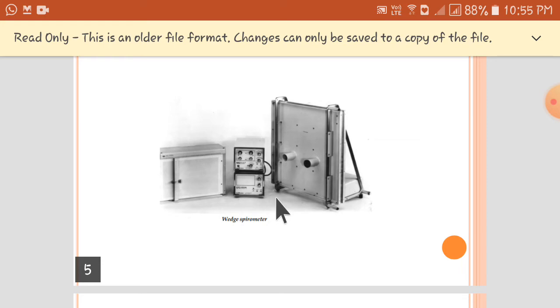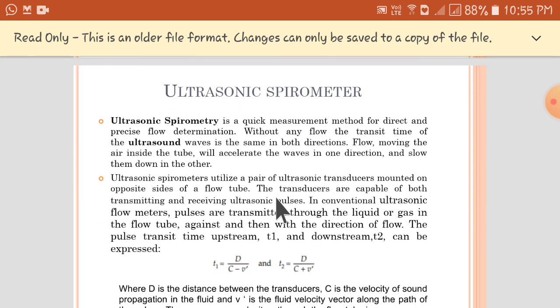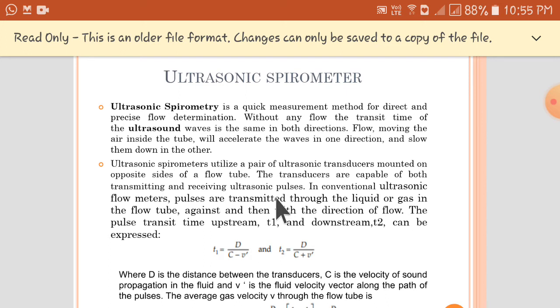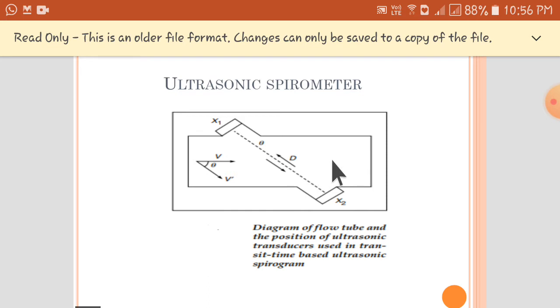Next we are going to discuss the ultrasonic spirometer. An ultrasonic spirometer utilizes a pair of ultrasonic transducers mounted on opposite sides of a flow tube. Suppose this is the flow tube. Two transducers will be attached at opposite sides of the flow tube. These transducers are ultrasonic transmitters and receivers. Both of them will be sending ultrasonic signals which will be received by the transducer at the opposite side. Now, if there is no flow of air inside the flow tube, what happens? The transit time of both the signals, that is the upstream transit time and downstream transit time, will be the same. But if there is flow in one direction, the transit time will not be the same.